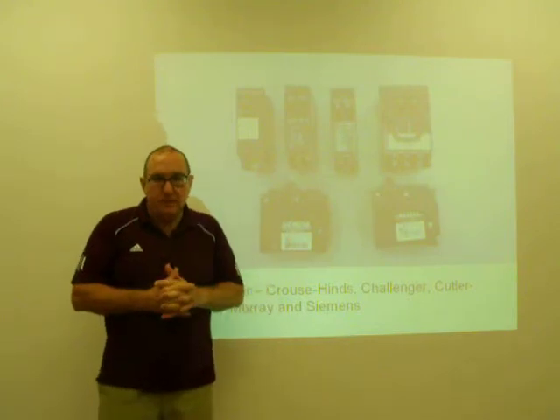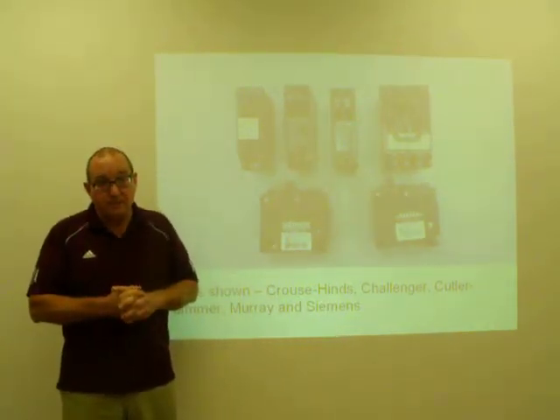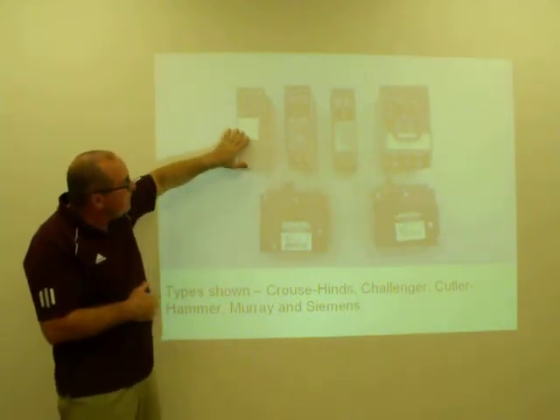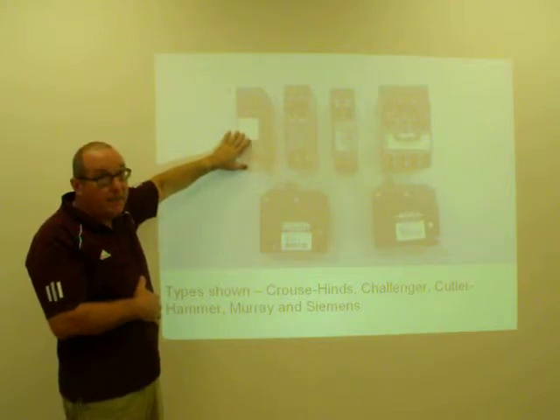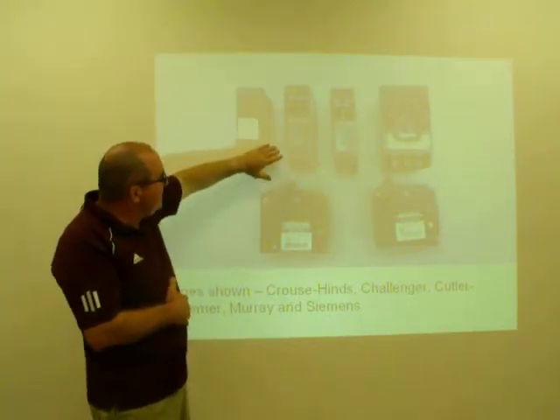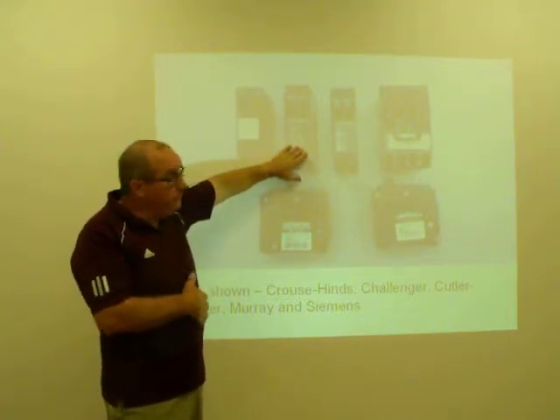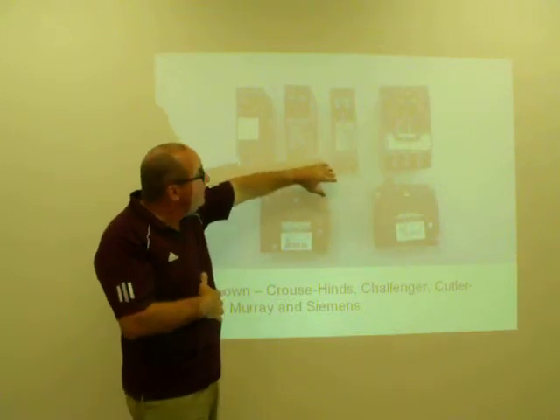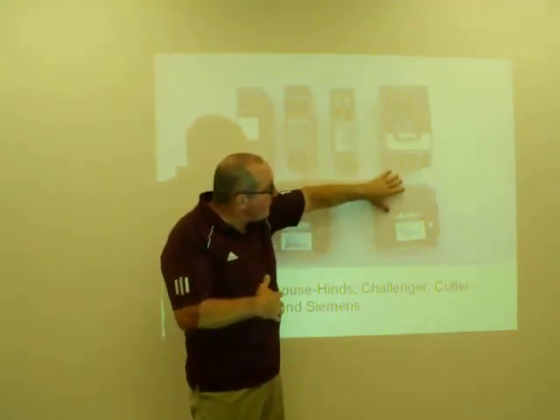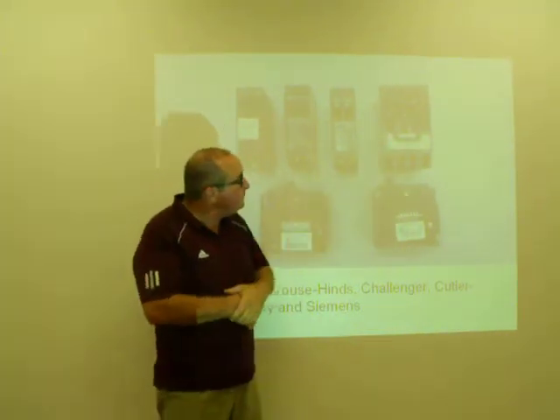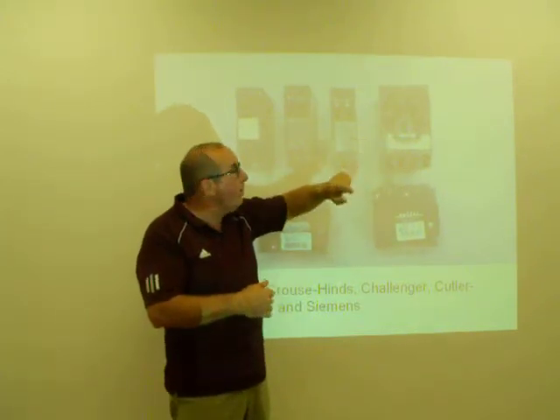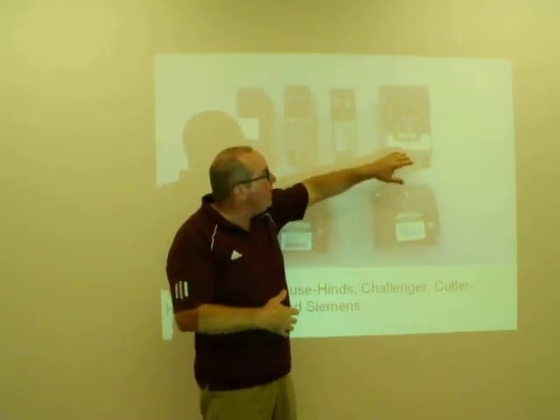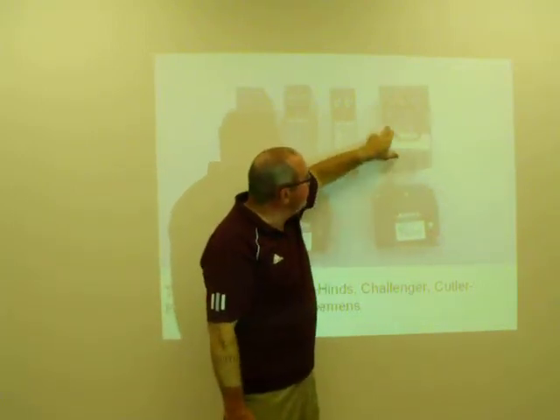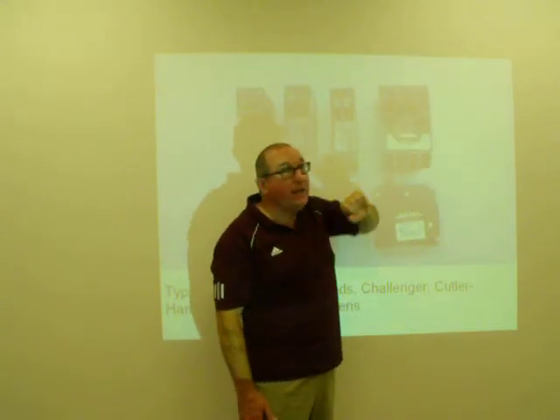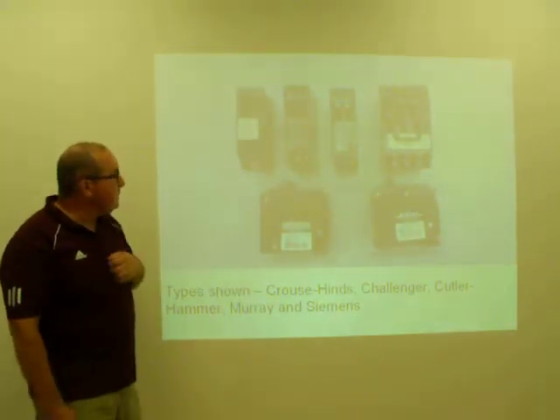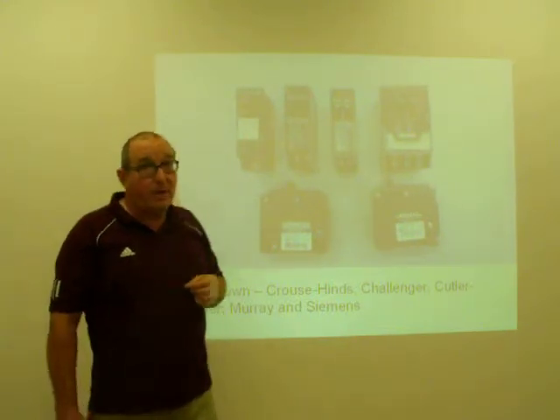Here's some of the breakers that I found in that panel board at the sports bar. And you can see here, you can't really read it here, but this is a Crouse-Hinds, which is not really available anymore. And this one is a Challenger, which is now owned by Eaton. This is a Cutler Hammer, which is now owned by Eaton. This is a Murray. These are actually two different Murray breakers, but I was showing the label on the side that you can't really see on here. And this is one of the famous Murray double twins, I call them, where you have two-pole breakers built in one. And so you have a handle tie that gives you a 40 amp pair, another handle tie up here that gives you a 20 amp pair. And then last but not least, a Siemens breaker. And there may have been a couple others in there, I just don't remember.